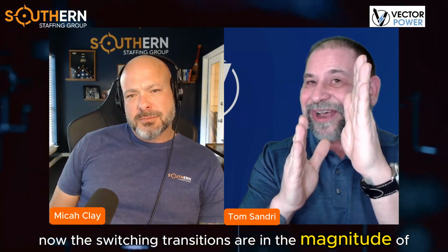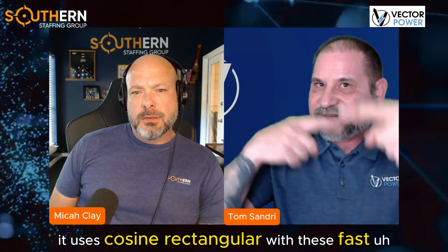Interesting. Now, the switching transitions are in the magnitude of 4 to 7-ish milliseconds. Nice and fast, just like your 60 hertz. So there is a technique out there. One of the terminologies I've heard for it is called the slope technology. It uses cosine rectangular with these fast polarity reversals. All of the white papers that I've seen from the European community on testing and side-by-sides at 60 versus cosine rectangular, they're showing gorgeous correlation to the 60 hertz test results. So there's the Paul Harvey rest of the story.